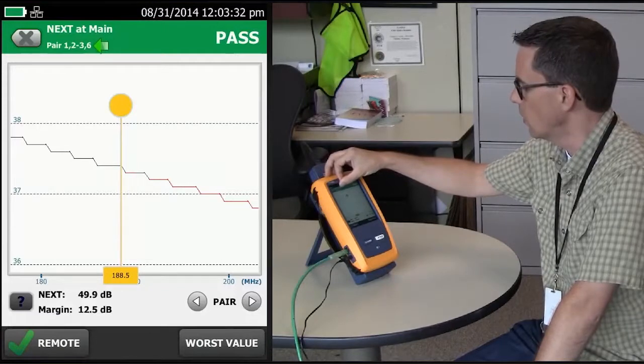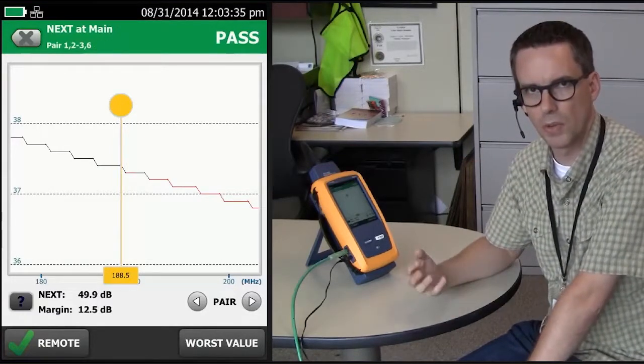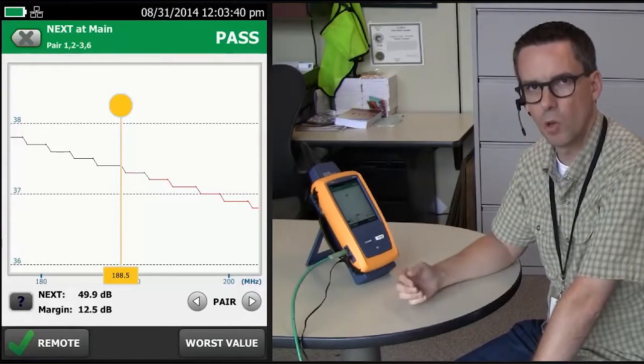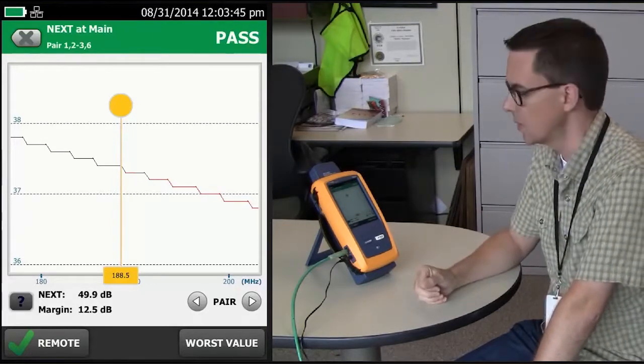This is for crosstalk on pair 1, 2, 3, 6. I said the 4 dB rule applies based on the insertion loss. Well, does it apply on the insertion loss of pair 1, 2 or pair 3, 6? It's pair 3, 6. That's how it's defined in the standards.